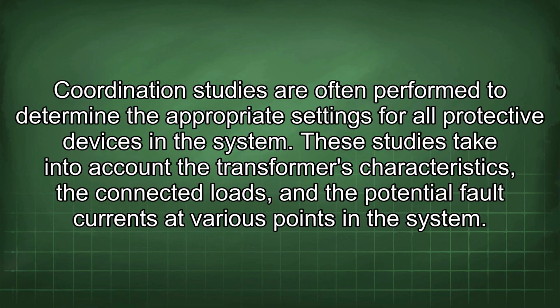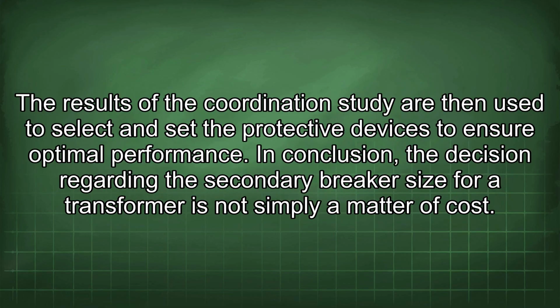Coordination studies are often performed to determine the appropriate settings for all protective devices in the system. These studies take into account the transformer's characteristics, the connected loads, and the potential fault currents at various points in the system. The results of the coordination study are then used to select and set the protective devices to ensure optimal performance.